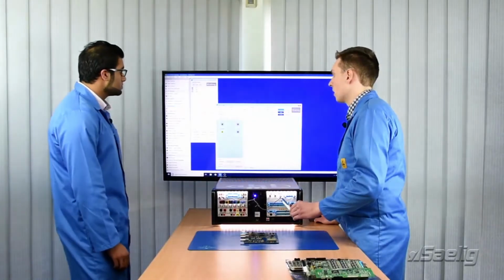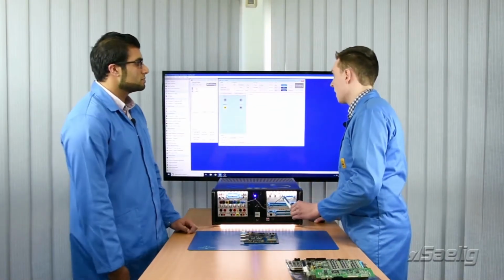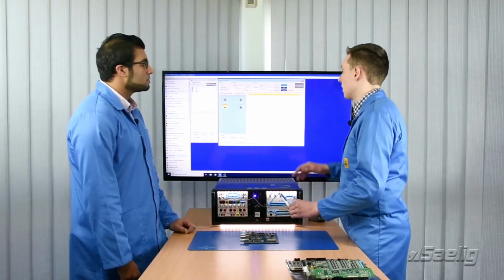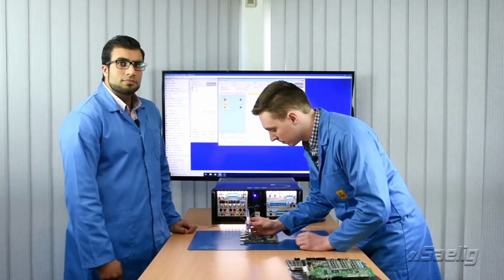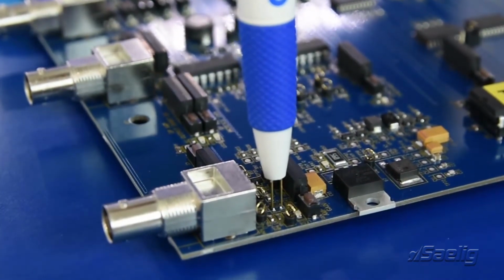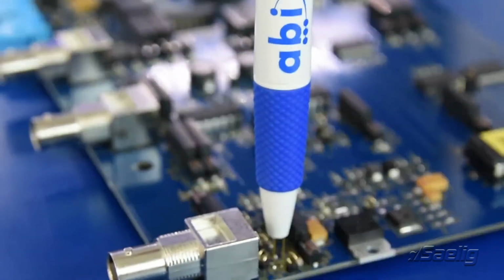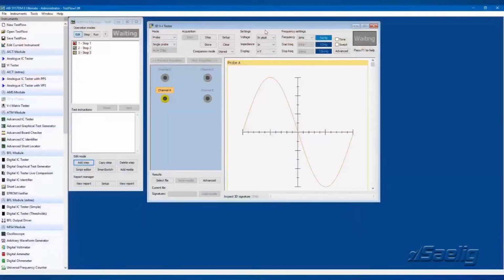So 3D VI, although in this case we set the mode to VT, so it's a VT test. And all we click is start, and it'll automatically show you that sine wave, and we'll interrupt that using our pulse output. There you go, just over. There we go, and we can stop that. If I was using the foot switch, I could stop that under the desk. And there's our signal. We can show that the sine wave's been interrupted by that pulse output.